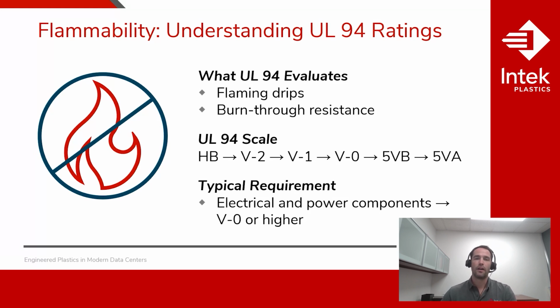And a V0 material would self-extinguish without any flaming drips. And this is a common requirement for electrical and power components that you might find in a data center. For the most demanding applications, you'd be looking at the 5V tests, of which there are 2 ratings. And this utilizes a specimen oriented horizontally with a flame applied underneath. For a 5VB specimen, you might have some surface damage or slight burn through. And for a 5VA rating, the specimen would resist burn through entirely. It's important to note that the flame source for the 5V tests is roughly 5 times more energetic than for the HB and the V0 tests.